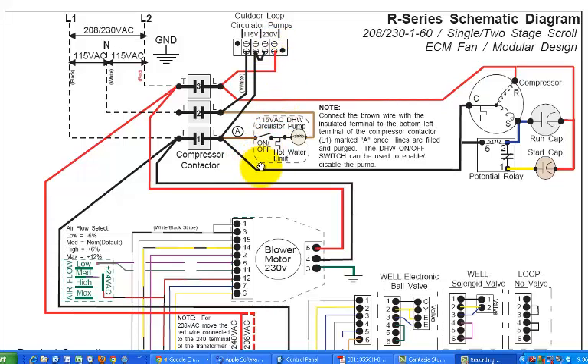Now, additionally, on the Nordic line of heat pumps anyway, with the de-superheater structure, it comes as a standard on them, and also standard with that is a built-in circulator pump. But it's a 115 volt circulator pump. So what do we do to make that run? Well, instead of pulling off the power from the L1 and the L2 terminal, we in this case are pulling it off the L1 and the neutral. So now that domestic hot water circulator pump operating the de-superheater structure, that is, of the refrigeration system, is operating on the 110 volts.